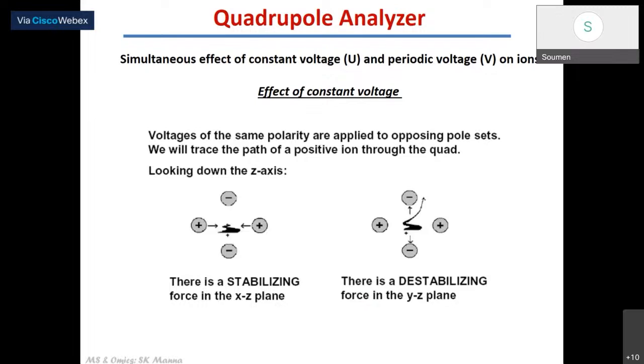In quadrupole analyzers, you have basically four poles. On these four poles, two kinds of voltages are being applied. Along the x direction, there is a positive voltage on both poles, and in the yz plane, there is negative polarity. The ion is moving along the z axis. Any ion will have a stabilizing potential along the xz plane, whereas it will be destabilized along the yz plane — if it is a positive ion; for a negative ion it will be the other way around. Typically, along yz it will be destabilized and along xz it will be stabilized.